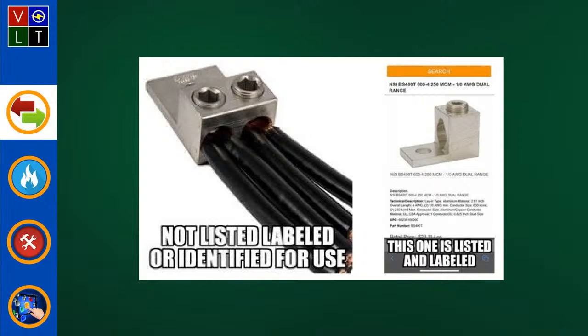And to me, I just thought, that's not right. But it could be listed and labeled for those conductors. Look at the one on the right, it has all the information listed there. It tells you can put two of any size, typically when you're paralleling it's going to be the same size conductor. But that wouldn't really prohibit you from using a different size if you were trying to do something else. It's kind of a gray area, usually when I do it they're equal size conductors, but if it's a listed lug that gives you that wire range, I don't see why you couldn't use that for a tap.